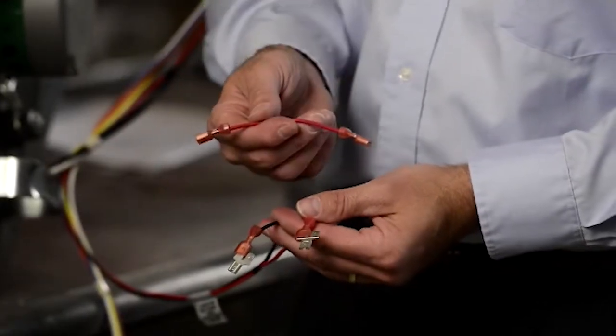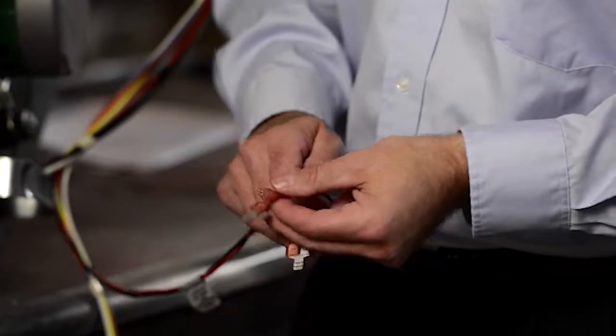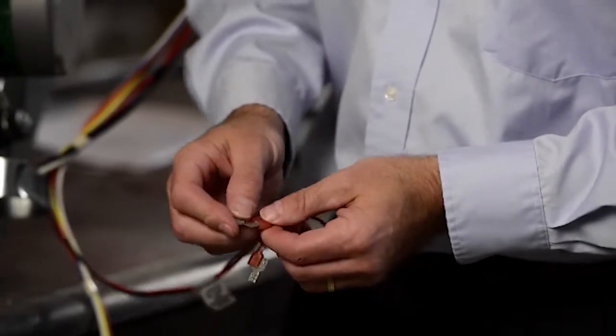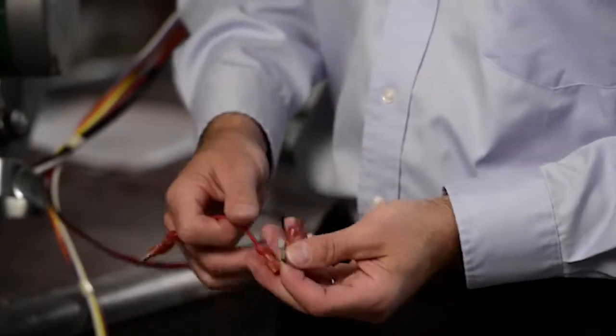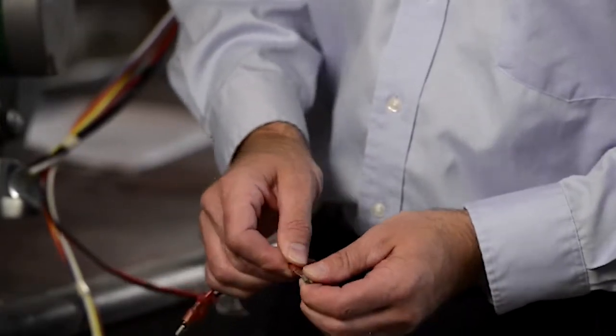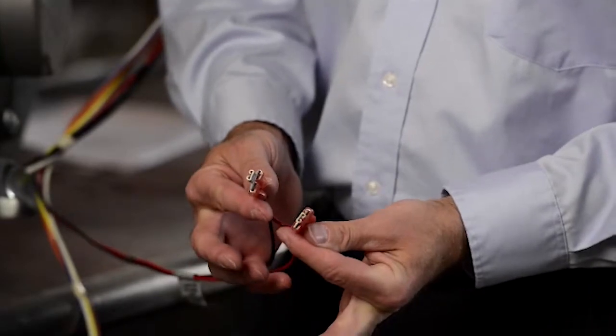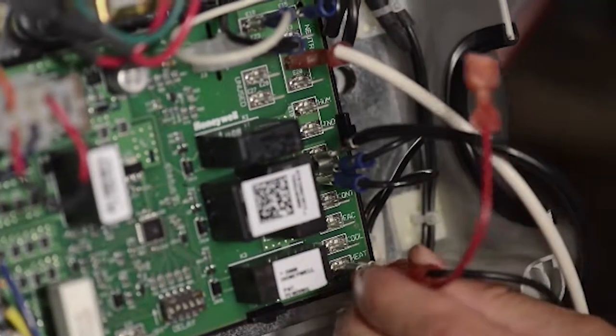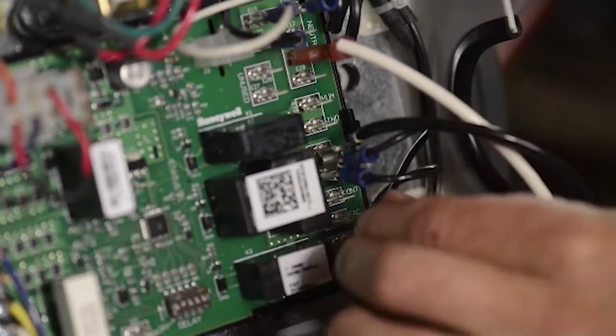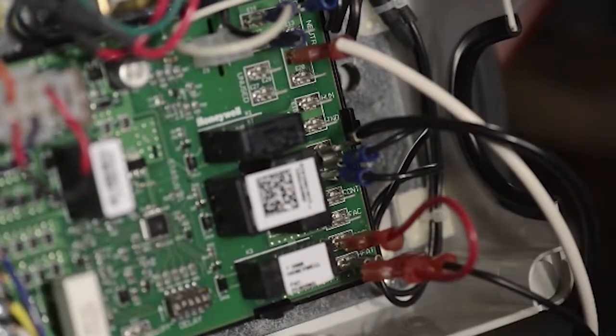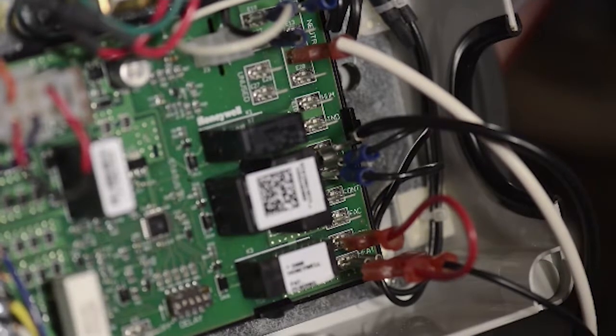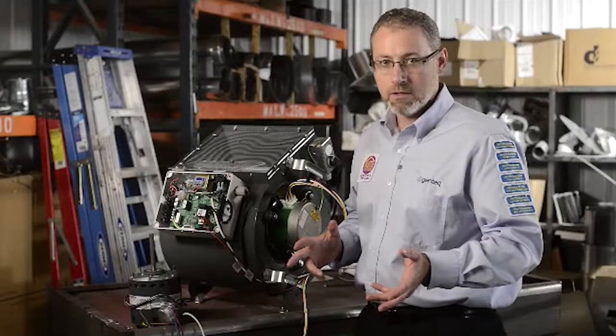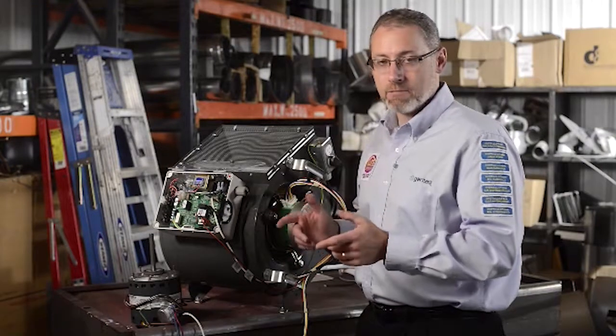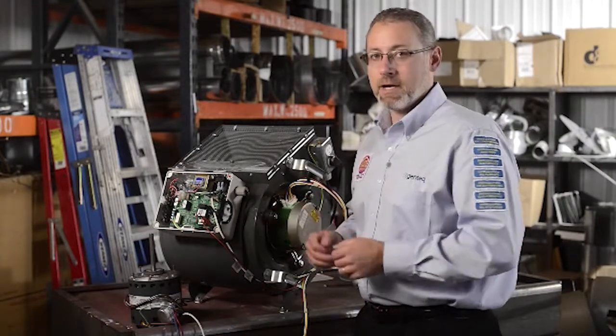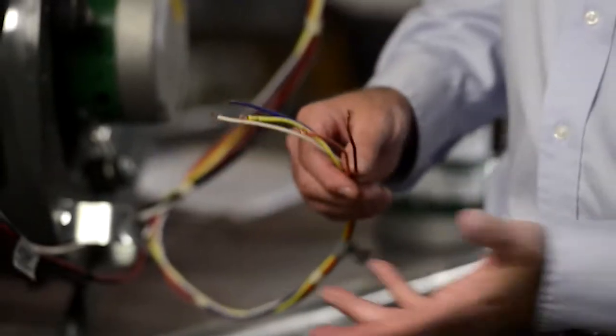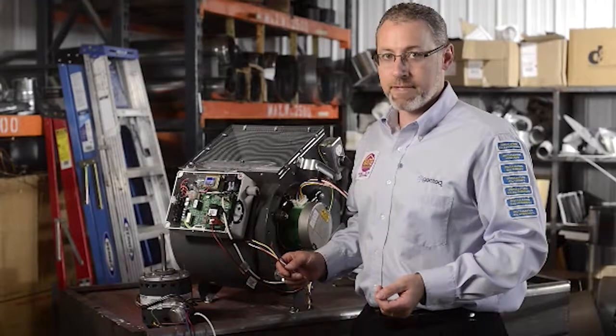So the first thing we're going to do is get our jumper wire out of our box of parts, and we're going to put it to 1 wire on the 1/4-inch Y connector, jumper that over to the other 1/4-inch Y connector, and then I'm simply going to connect these two terminals to the heat and cool taps on my system control board. What that's going to do is make sure that regardless of whether there was a heat call or a cool call, I run both the black and the red wires for my on command and my horsepower selection.